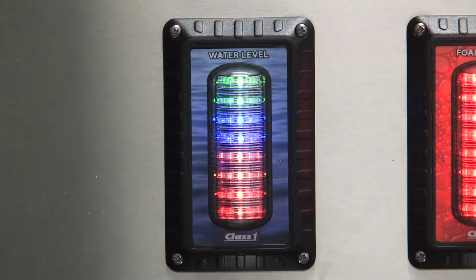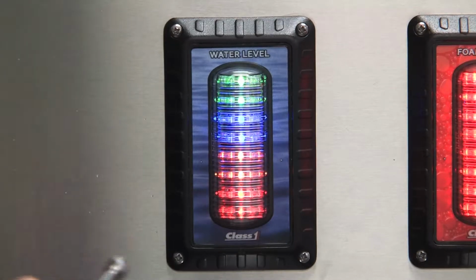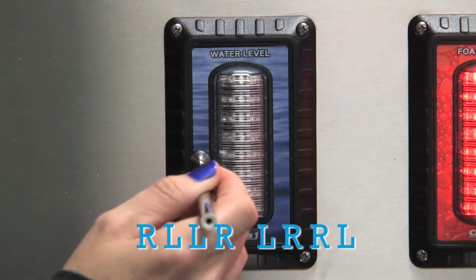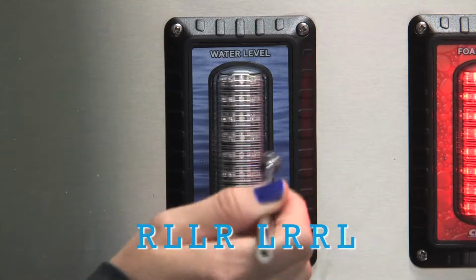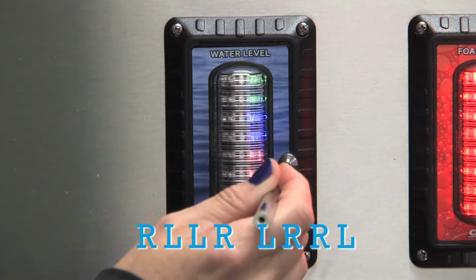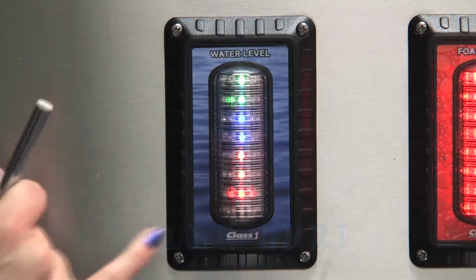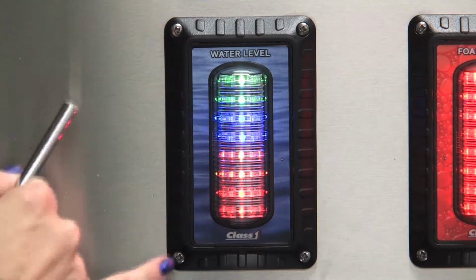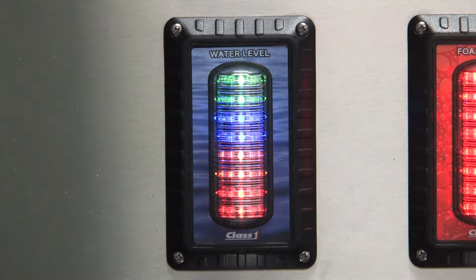To do the 1-point calibration, the sequence is right, left, left, right, left, right, right, left. Number 1 is displayed, and now it shows full. Your unit is calibrated. Make sure you start with a full tank, and the display will then calibrate the empty point, which will be 0.55 volts or about a half inch of liquid in the tank.